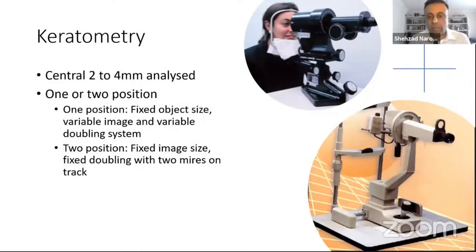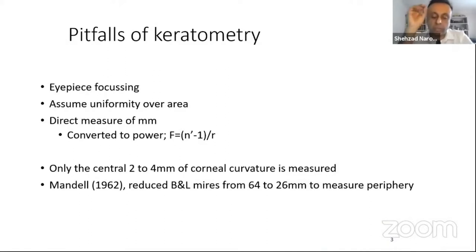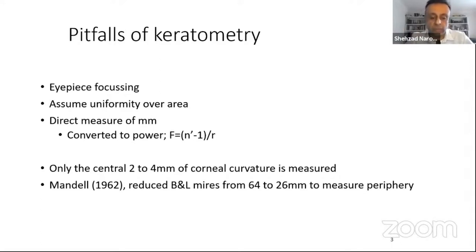Most of us use a keratometer — a manual keratometer or the auto refractor/auto keratometer type device — and with these devices we look at central corneal curvature. We have the one- or two-position type keratometers, traditionally the Bausch & Lomb style, the Zeiss style, and the Javal-Schiøtz type. A main pitfall with a manual keratometer is eyepiece focusing: when students take K readings, you often find small differences because they haven't focused the eyepiece correctly.